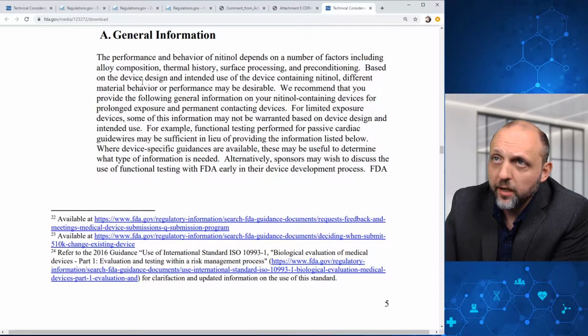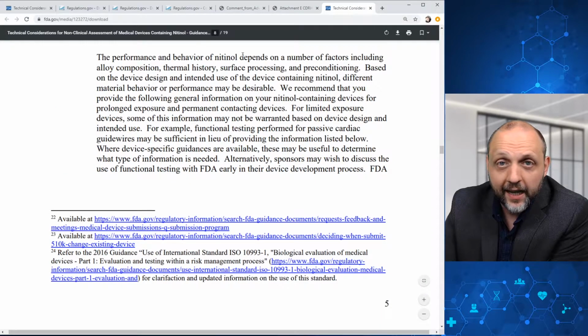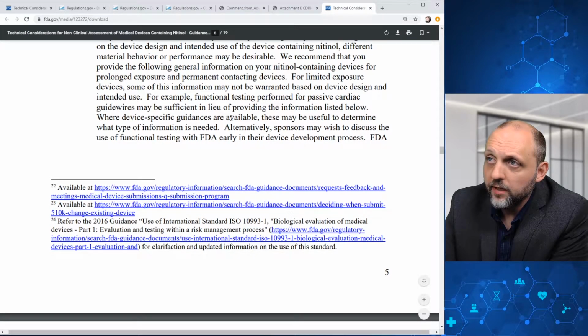And then in terms of general information, here FDA calls out that the performance and behavior of nitinol depends on a number of factors, including alloy composition, thermal history, surface processing, and preconditioning, and based on the device design and intended use, different material behaviors or performance may be desirable. And FDA recommends to provide the following general information about the device for prolonged exposure and permanent contacting devices. And for limited exposure devices, some of this information may not be warranted based on device design and intended use. And again, they call out where device-specific guidances are available. These may be useful to determine what type of information is needed.